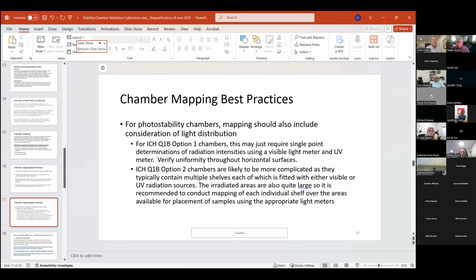Q1B option 2 chambers are likely to be more complicated because they typically contain multiple shelves, each of which is fitted with either visible or UV radiation sources. The irradiation areas are also quite large, so it is recommended to conduct mapping of each individual shelf over the areas available for placement of the samples using the appropriate light meters.